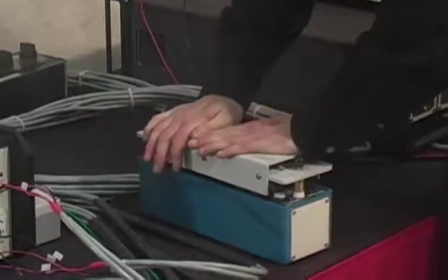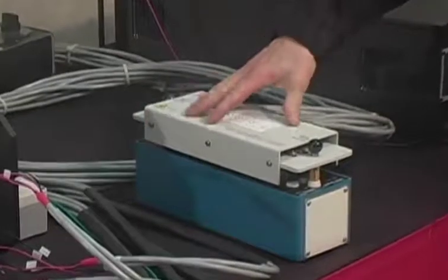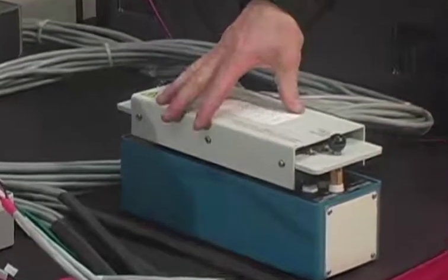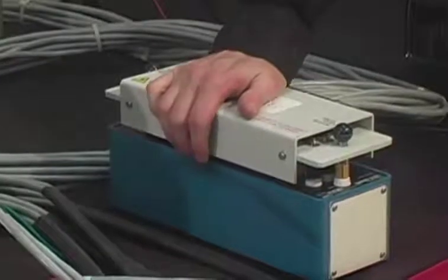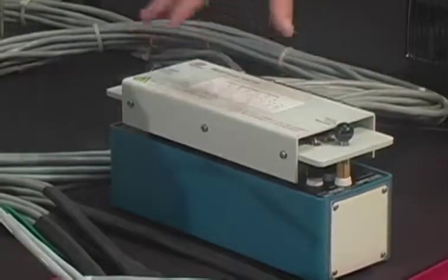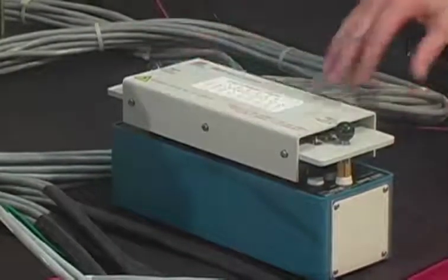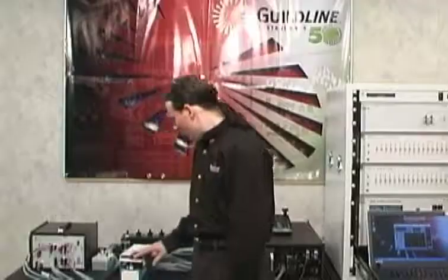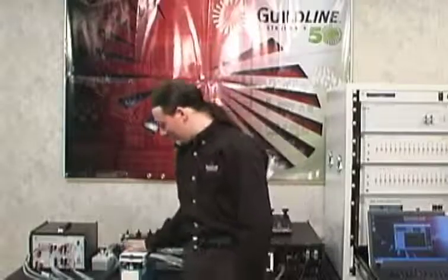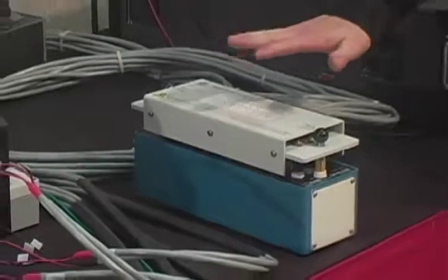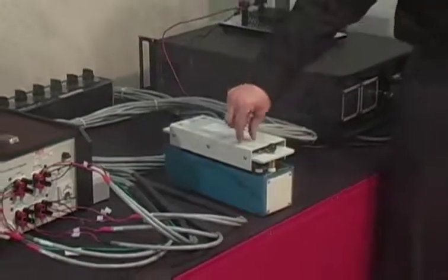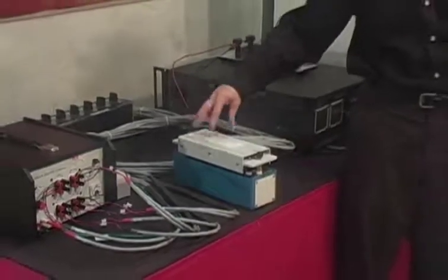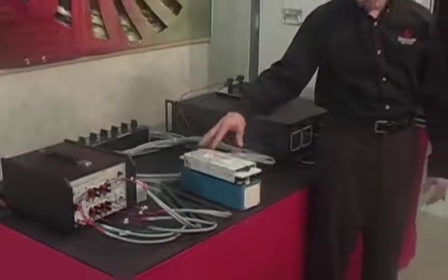It's quite stiff because you are plugging in about 24, 25 banana jacks. So it takes a fair amount of force to actually put it in there, but make sure you've got a good secure connection, because the integrity of your connections, of course, will dictate the quality of your measurement. So with this thing connected, then you're able to start to run the transfer standard utility. So this example here, I'm using a 1 ohm per step, which means it's got 12 1 ohm resistors inside this Hamon standard that are going to be measured.